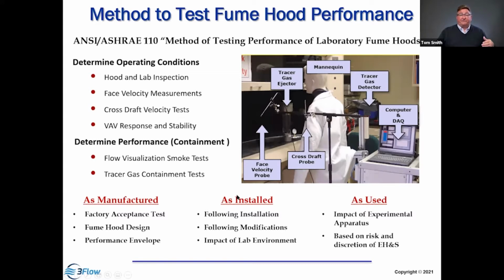After it's installed and before it gets used for hazardous materials, we want to look at the commissioning of that hood and the impact of the hood design and the lab environment on its operation. And then finally, the as-use test is after they set up their experimental apparatus. What is the impact of the experimental apparatus on containment? The last test, the as-used, is really at the discretion of EH&S. If there is a sense that the apparatus and the process or procedures are going to influence containment, then it may be necessary to specify an as-used test.